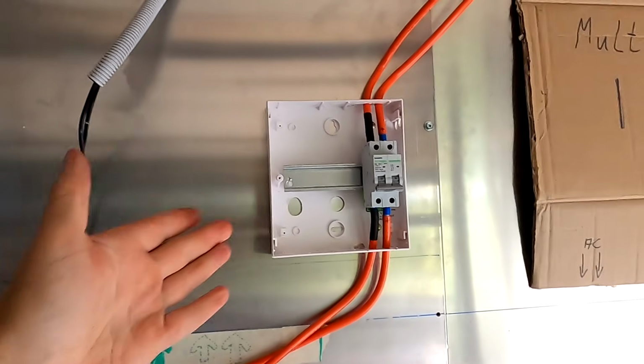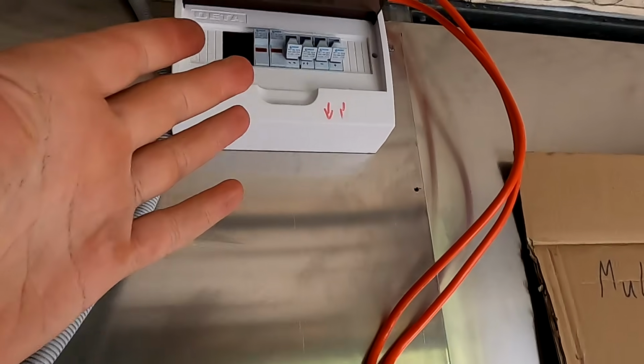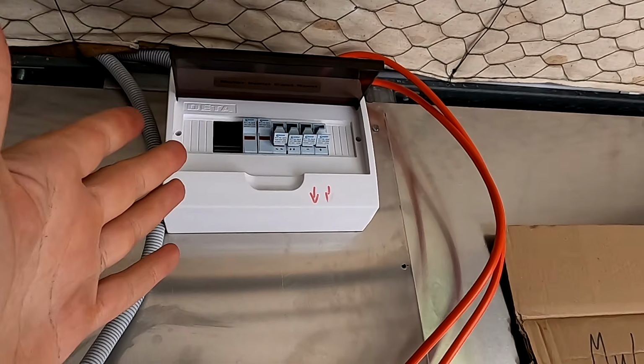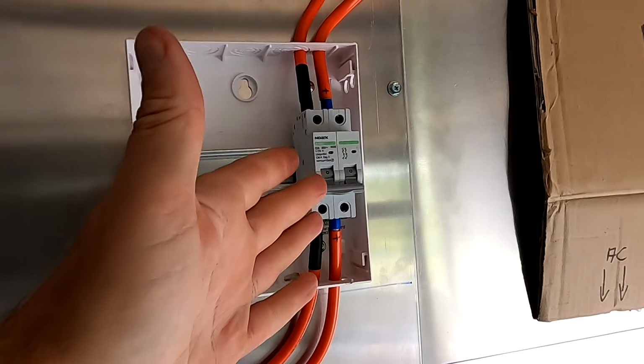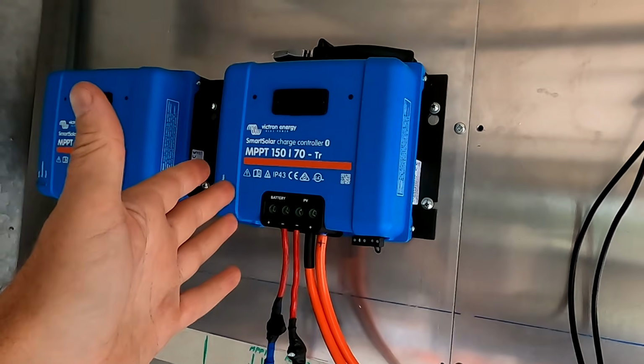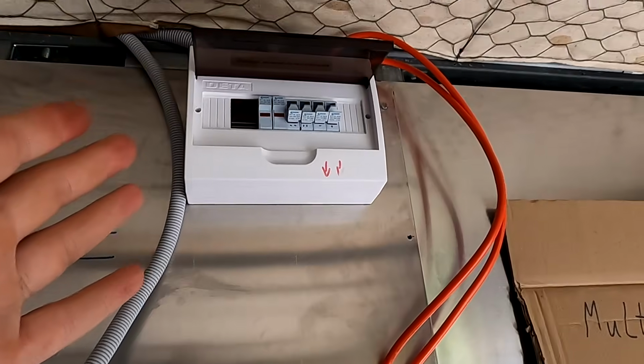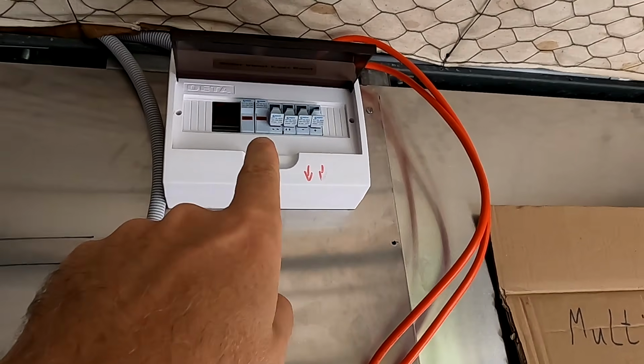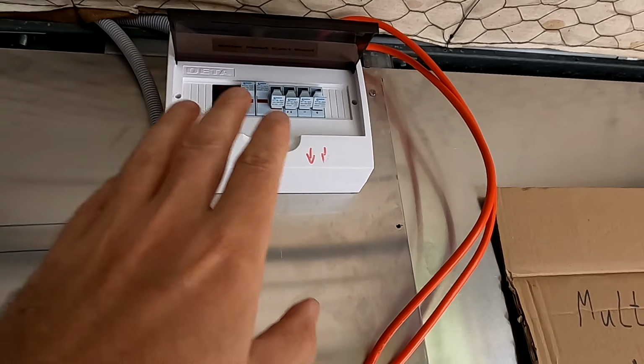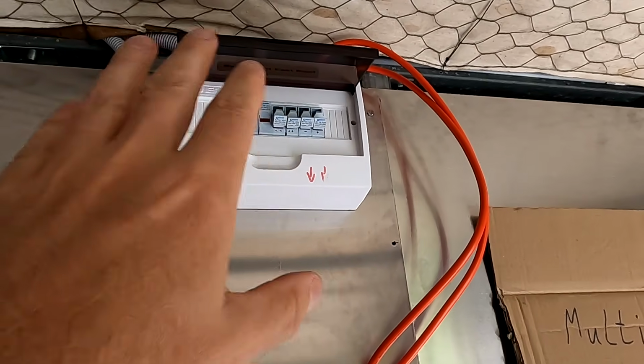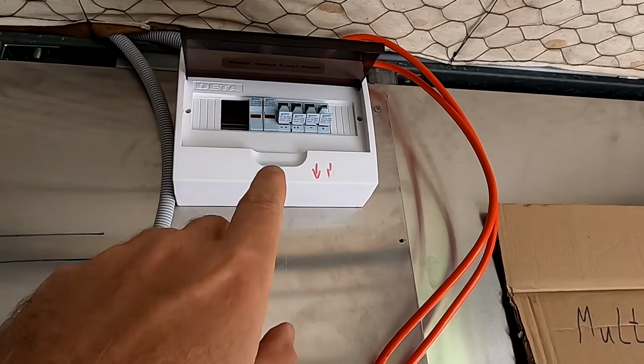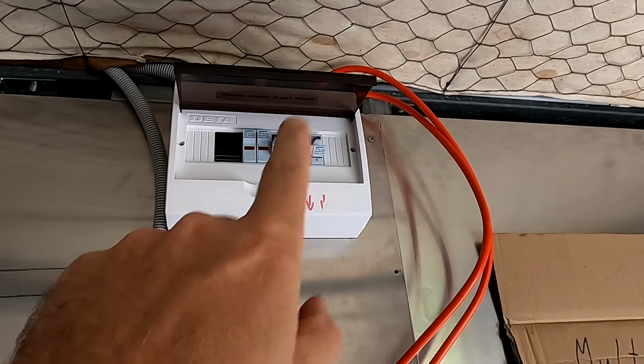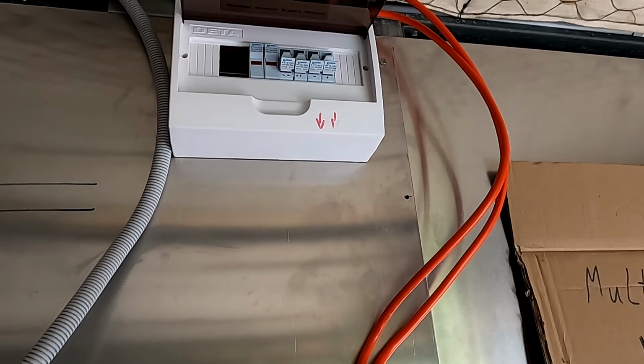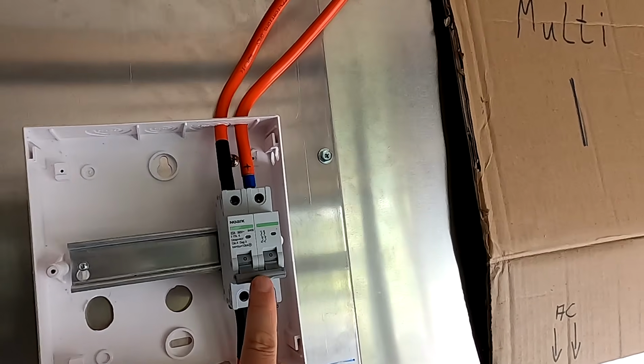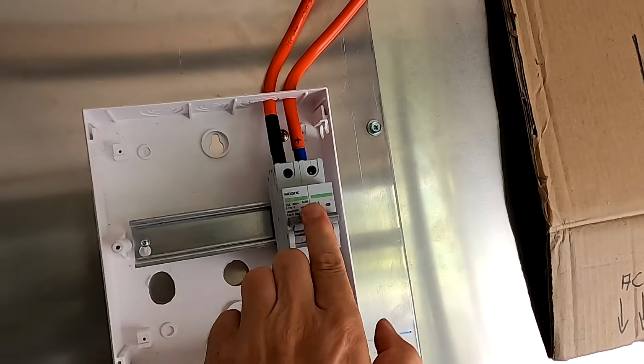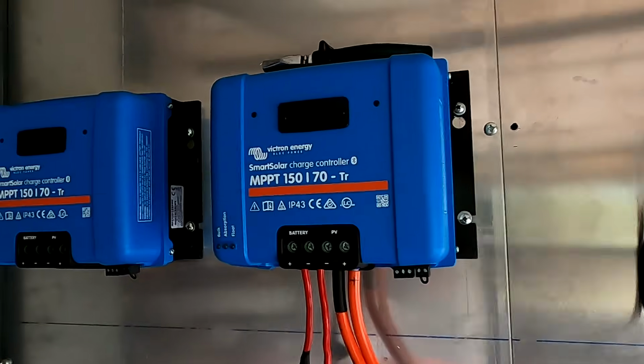Now you can see what this circuit breaker is for — we can isolate single strings up there, but there's no current going to the solar charge controller. So in case of a fault on the roof, I can isolate single strings completely, positive and negative, work on them on the roof without worrying about anything else, and leave the other strings connected. Then when everything's ready, we push this one in, and hopefully we'll have a charge.